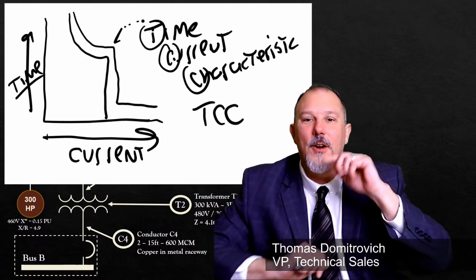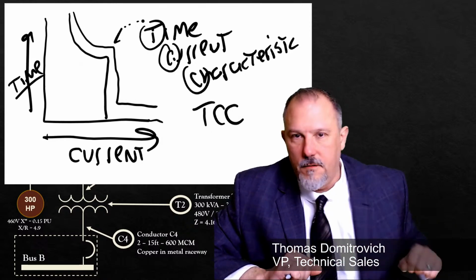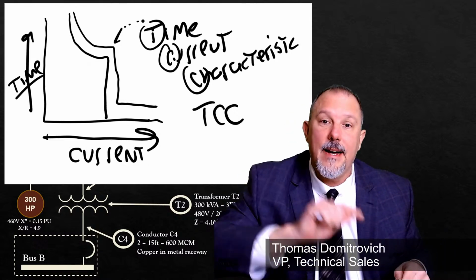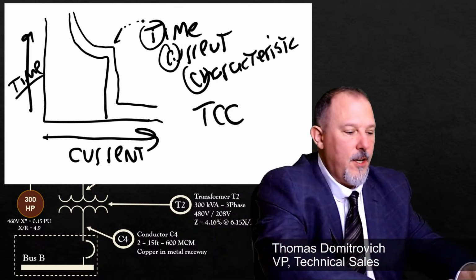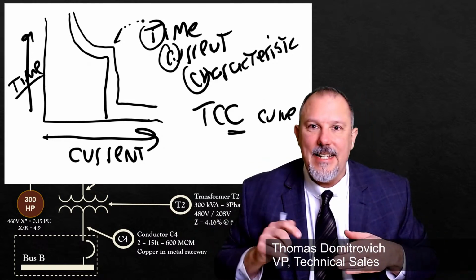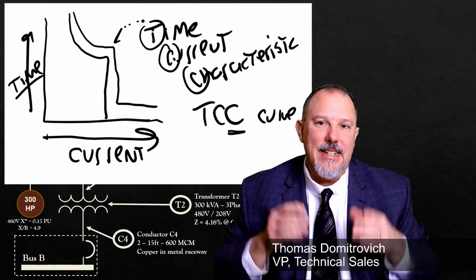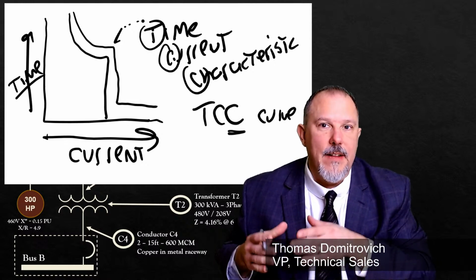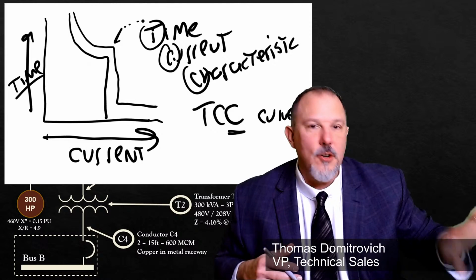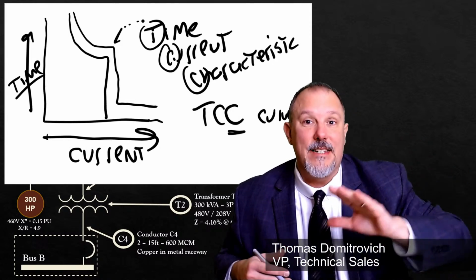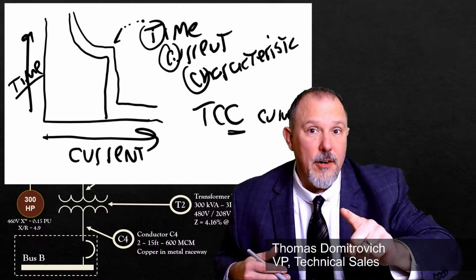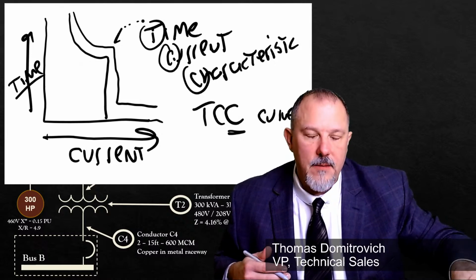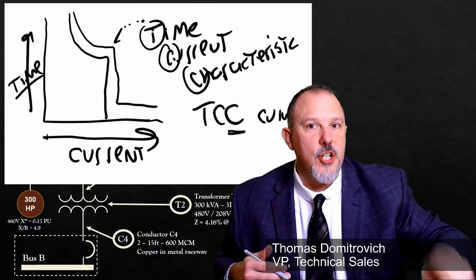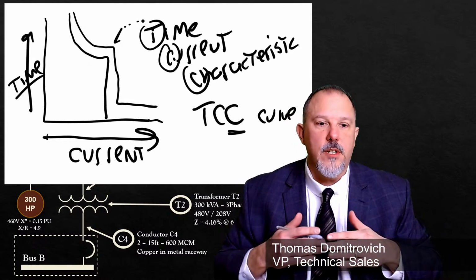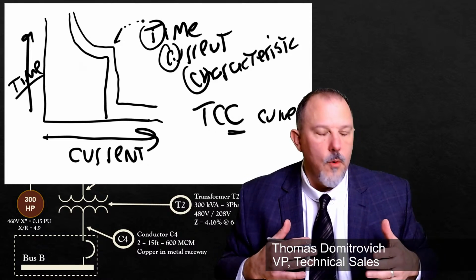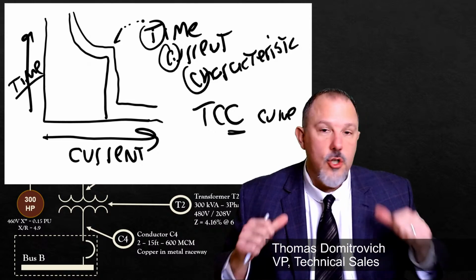TCC. Now, there are a lot of people who say TCC is time current curve, and I'm telling you, you are wrong. It is time current characteristic, and then you have curve. That third C is important. We debated that C at some NEMA meetings and IEEE meetings, Institute of Electrical and Electronic Engineers. It is a time current curve, but it is a specific characteristic of that device, and every device will have different characteristics. So don't underestimate the power of that third C. It is not time current curve. We all take shortcuts in a lot of different ways. Don't take shortcuts when we're talking about a TCC curve, because you're going to get me mad, all right? Don't want to get me mad.